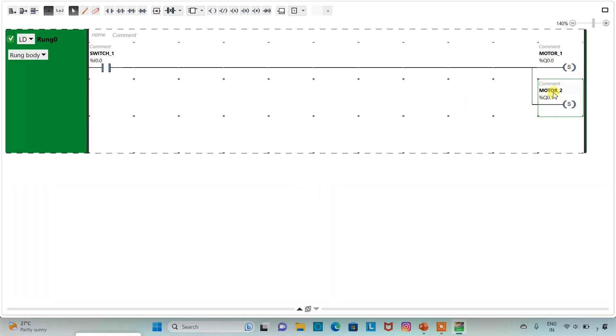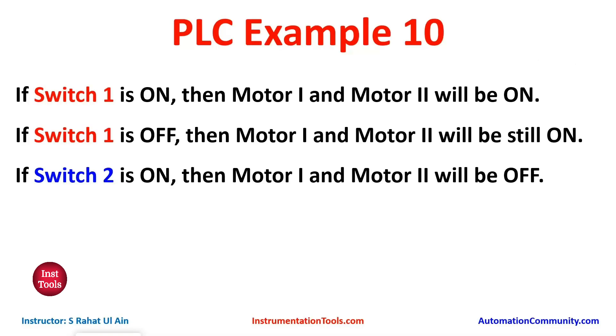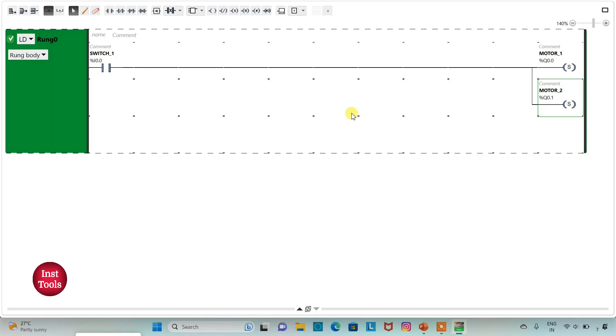So we have used two set coils here. That is, when switch1 is on, motor 1 and motor 2 will be on. And then, if we turn off switch1, the outputs will remain on — that is, motor 1 and motor 2 will be still on. Then if switch2 is on, then motor 1 and motor 2 will be off. So to turn off these motors, we will use switch2, and we will use reset coils to turn off motor 1 and motor 2.